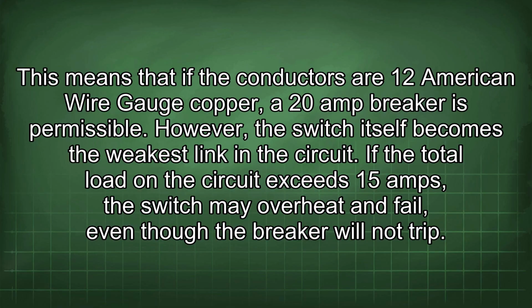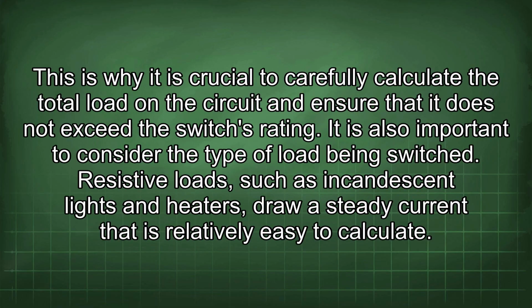If the total load in the circuit exceeds 15 amps, the switch may overheat and fail, even though the breaker will not trip. This is why it is crucial to carefully calculate the total load on the circuit and ensure that it does not exceed the switch's rating.